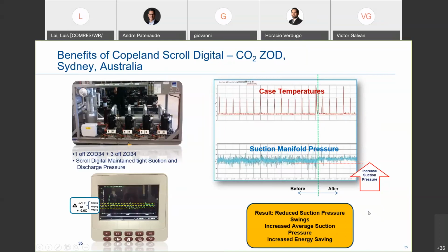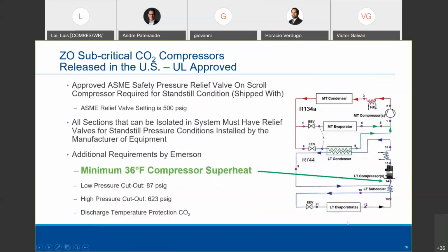The last thing on the compression I wanted to point out is super important: the superheat at the inlet of a low temp compressor must be 36 degrees or even higher. You say, wow, that seems excessive. Well, the medium temp compressors are 20 degrees, and the low temp are 36 degrees. And I'm talking Fahrenheit now. And there's a reason for that.